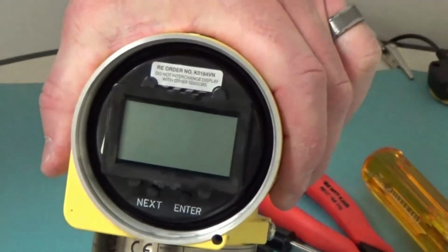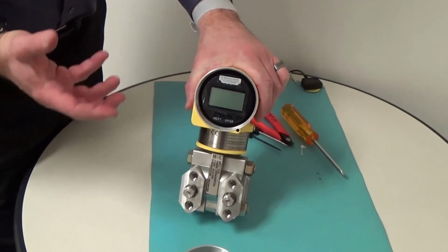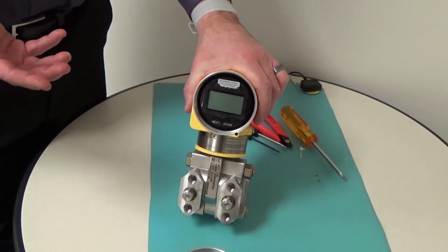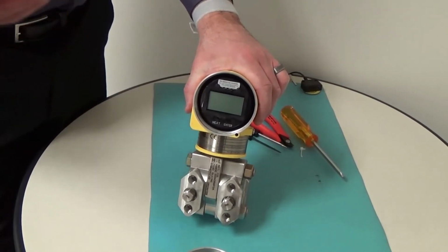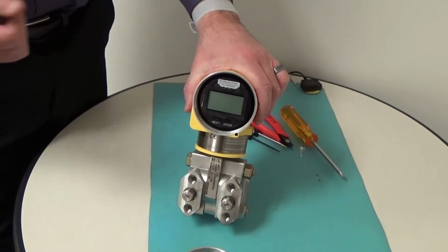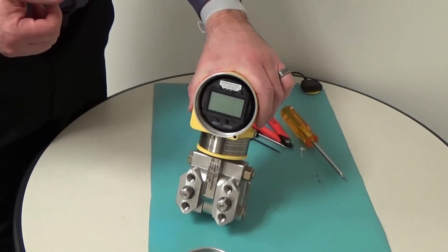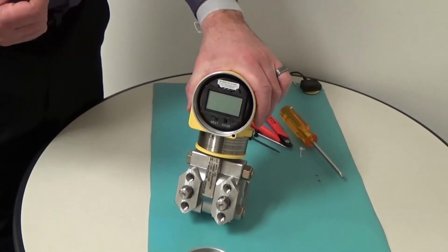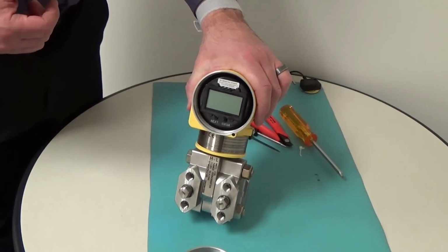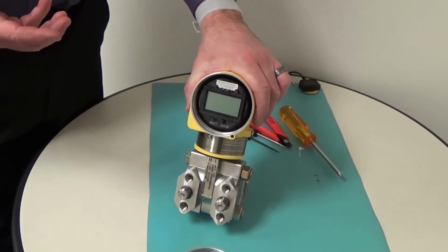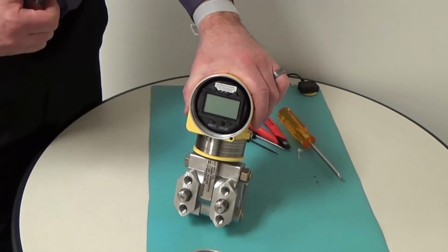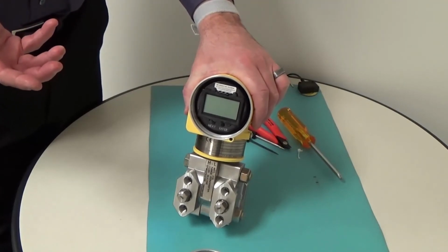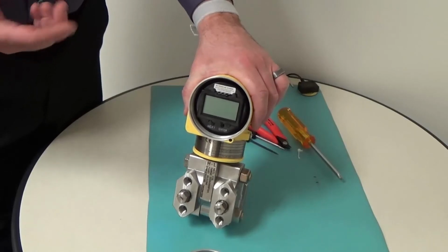So one of the things to be aware of in regard to the battery is that it is feasible to set up a register assignment so that you can monitor the battery voltage through the host and set up alarms on it. So the battery voltage shows up in the register as a value which is 1000 times the actual voltage. So for instance, these batteries are 3.6 volt batteries, so you'll see a new battery show up as a value of 360, and if that value gets down to, let's say, 300, which is 3 volts, that's an indication that the battery needs to be changed.